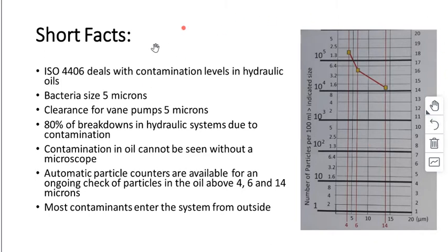Okay, just a couple of facts. ISO 4406 is the ISO standard that deals with contamination levels in hydraulic oils. Just to let you know that there is an International Standards Organization standard that deals with all this. And bacteria, again just to reiterate, has a size of 5 microns, and the clearance for vane pumps is 5 microns.